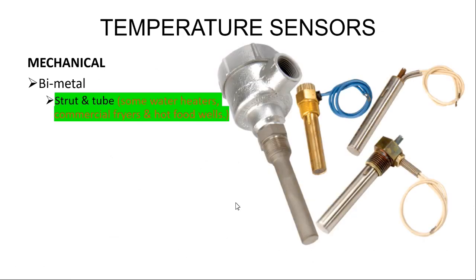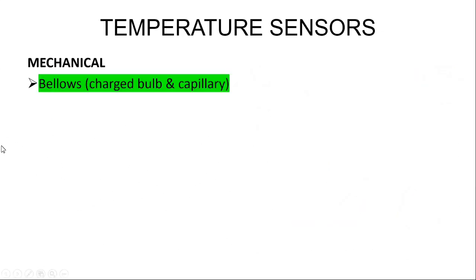Here are some other examples of the strut and tube. Each of these have some mechanical means in order to adjust the temperature. It should be noted that these can be designed to also make or break at a fixed temperature to serve as a high limit, like in a commercial fryer.